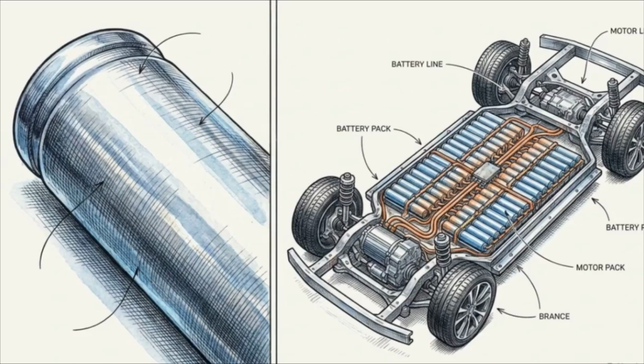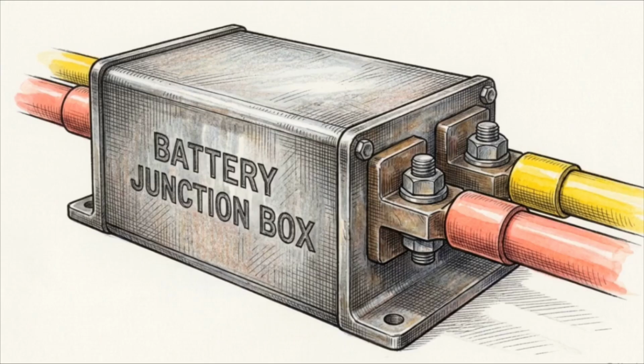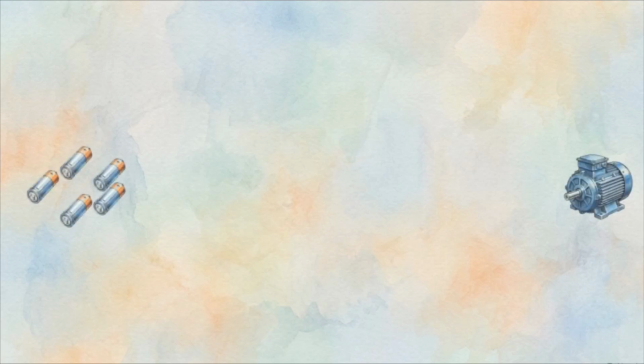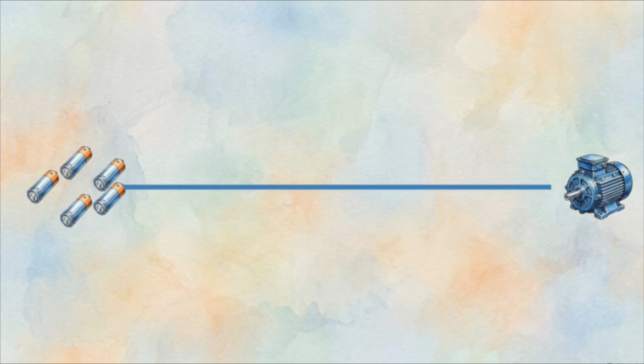While the CMU provides microscopic visibility into every individual cell, the system also requires macroscopic context of the pack as a whole. That macroscopic data is captured by the second physical module, the Battery Junction Box, or BJB. The BJB's primary data acquisition role is measuring the total magnitude of current flowing into or out of the complete system.